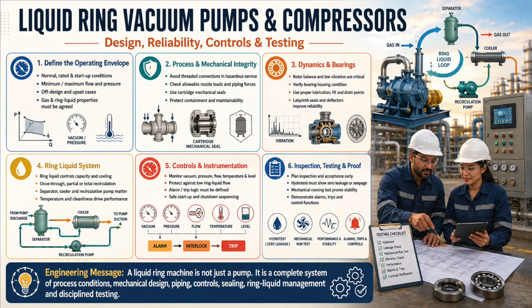Have vibration and bearing temperatures stabilized within acceptable limits? Have the controls actually been function tested? Have alarms, permissives, and trips been demonstrated? Have site piping loads and alignment tolerances been checked? Those questions separate a purchased package from an engineered system. That is the standard you should apply to every liquid ring vacuum pump and compressor you specify, review, inspect, commission, operate, troubleshoot, or inherit.